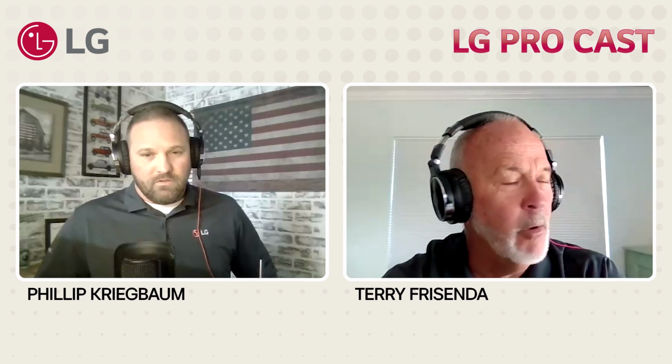You know, Philip, that's probably one of the most misused terms when we talk about VRF. If you talk to the commercial sector, exactly what you said. They think it's for the big jobs, the hospitals, the 10-story, 20-story buildings. But man, I got to tell you, a VRF system is an inverter-driven compressor that's changing hertz, electronic expansion valves, PCBs, right? And then a bunch of logic built into computer chips that basically drives and changes the hertz of a compressor and allows the correct, variable amount of refrigerant to be delivered to the indoor units as needed, when needed.